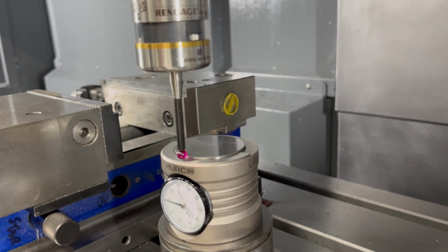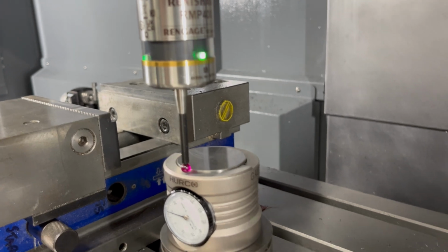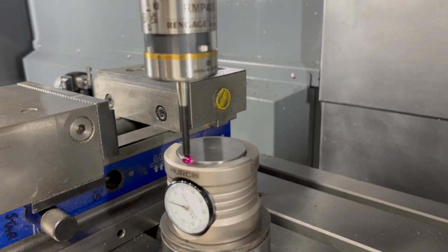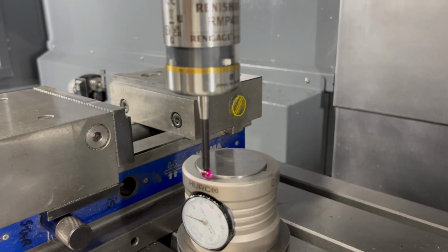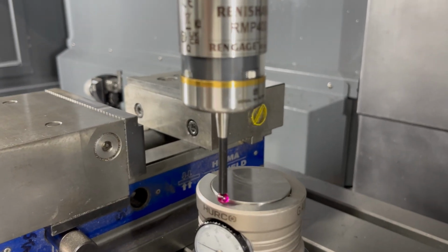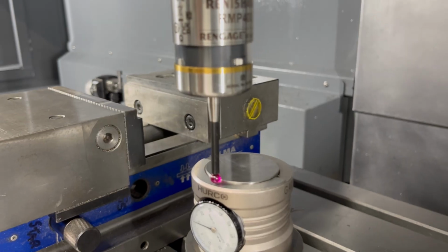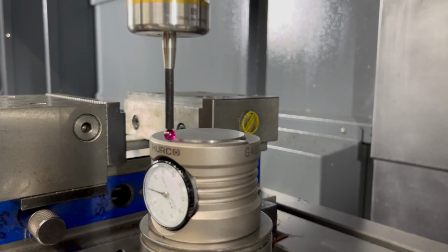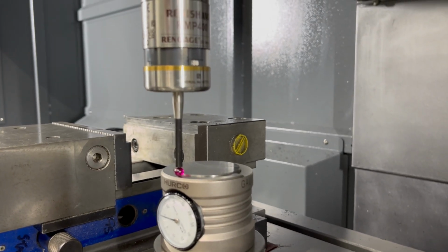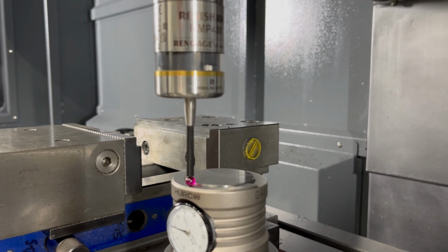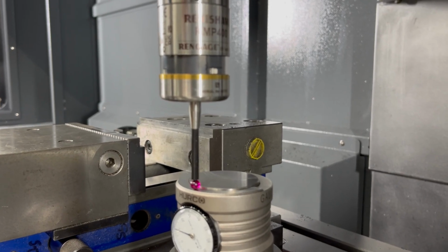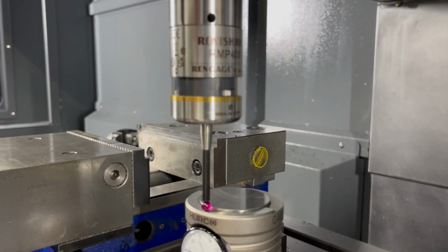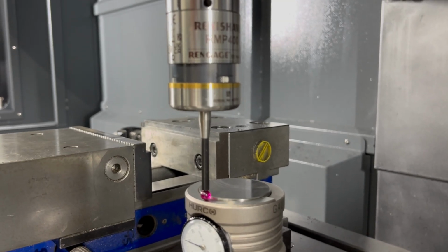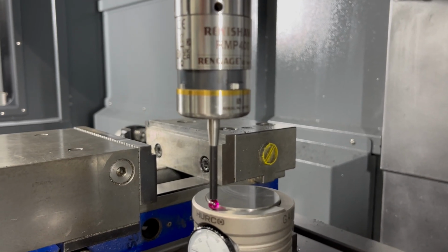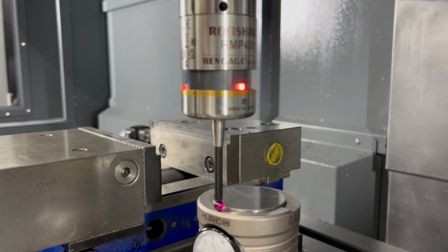What we're going to do is we're going to not touch on the moving pad, because if it was a solid tool, we would probably want to touch on that moving pad, but because the probe moves, we don't want to touch on that moving pad because we don't know which bit's going to move, whether the pad's going to move or the probe's going to move, and then there's going to be some inconsistencies. So we want to touch on a solid face, which is that shiny face on top, which normally goes flat when you push the pad down of the height gauge. So we're going to touch on there.